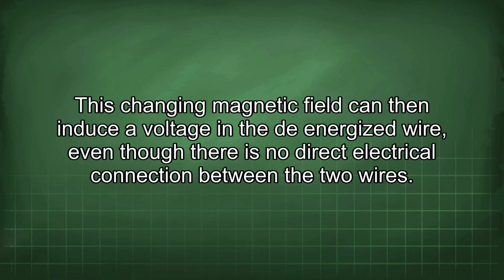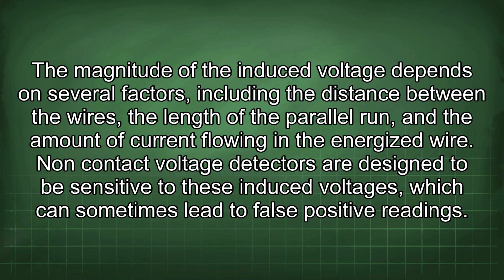This changing magnetic field can then induce a voltage in the de-energized wire, even though there is no direct electrical connection between the two wires. The magnitude of the induced voltage depends on several factors, including the distance between the wires, the length of the parallel run, and the amount of current flowing in the energized wire. Non-contact voltage detectors are designed to be sensitive to these induced voltages, which can sometimes lead to false positive readings.